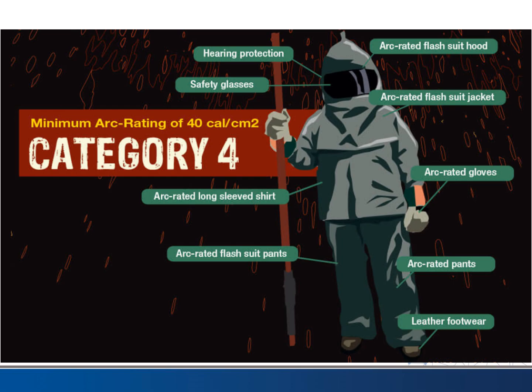When we do arc flash studies, if we have anything rated above a category two — which is where you have to put on the beekeeper suits — we'll do some investigating to see if we can find ways to reduce that category. Sometimes we can change out a breaker, use a more highly-rated breaker or something like that, and we can reduce it, but more often than not we can't.